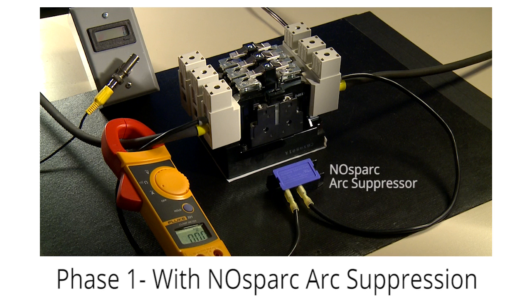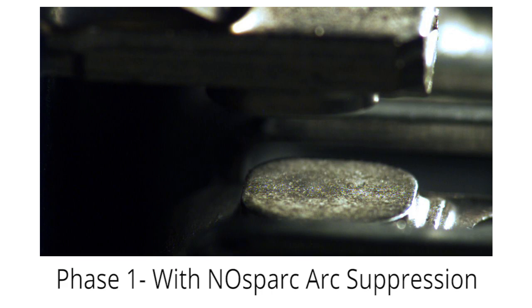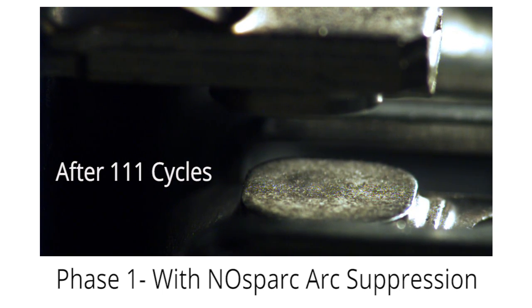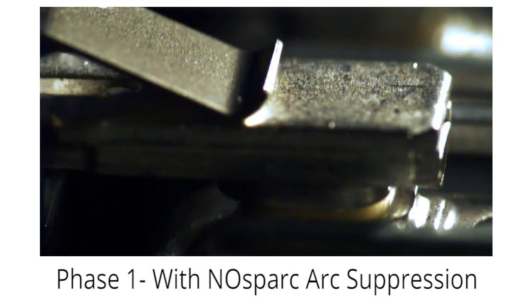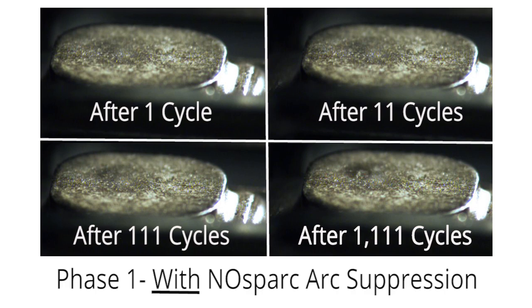In phase one, we connected our single-phase NOsparc arc suppressor across one leg of the power contactor, then connected the arc welder directly into the same leg. We set the arc welder at 235 amps — the maximum allowable current rating of our NOsparc arc suppressor. We set up our high-speed camera and ran the contactor through the following contact cycles: 1 cycle, plus 10 additional cycles, plus 100 additional cycles, plus 1000 additional cycles, for a total of 1,111 cycles — all suppressed by a NOsparc arc suppressor. We captured video of the contact cycles and shot close-up images of the contact surfaces after each waypoint.